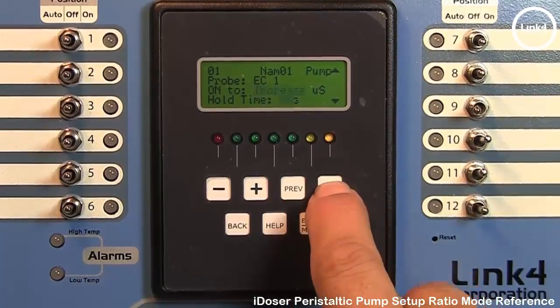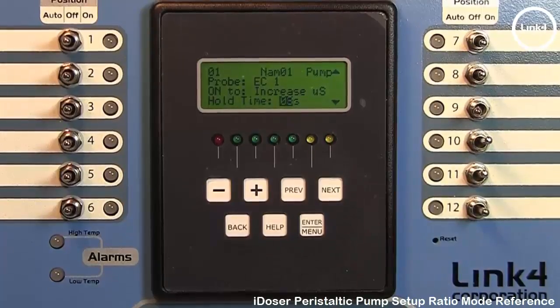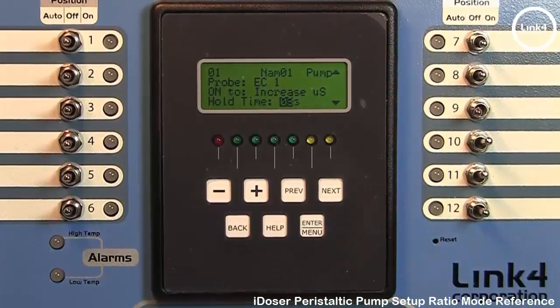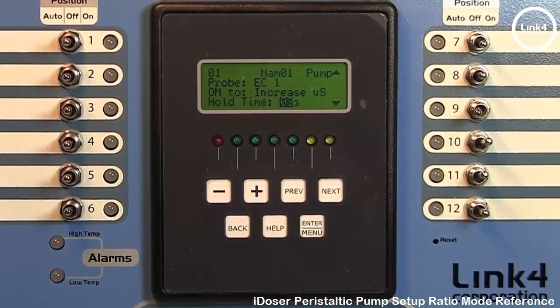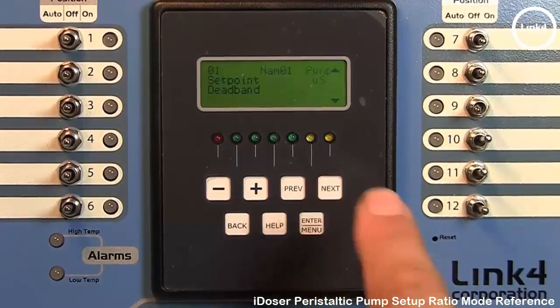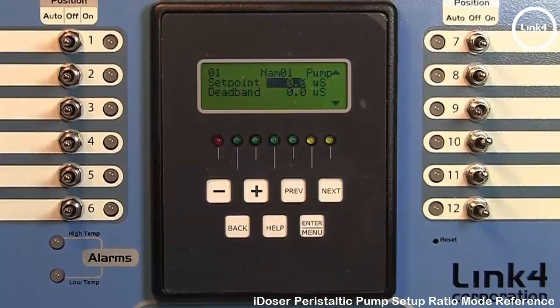Hit next. And we have hold time. Now the hold time is basically another dead band. Simply summarized, this probe reading must be above or below the set point for this duration, the hold time, before the injector pump will in fact be turned on. Hit next.